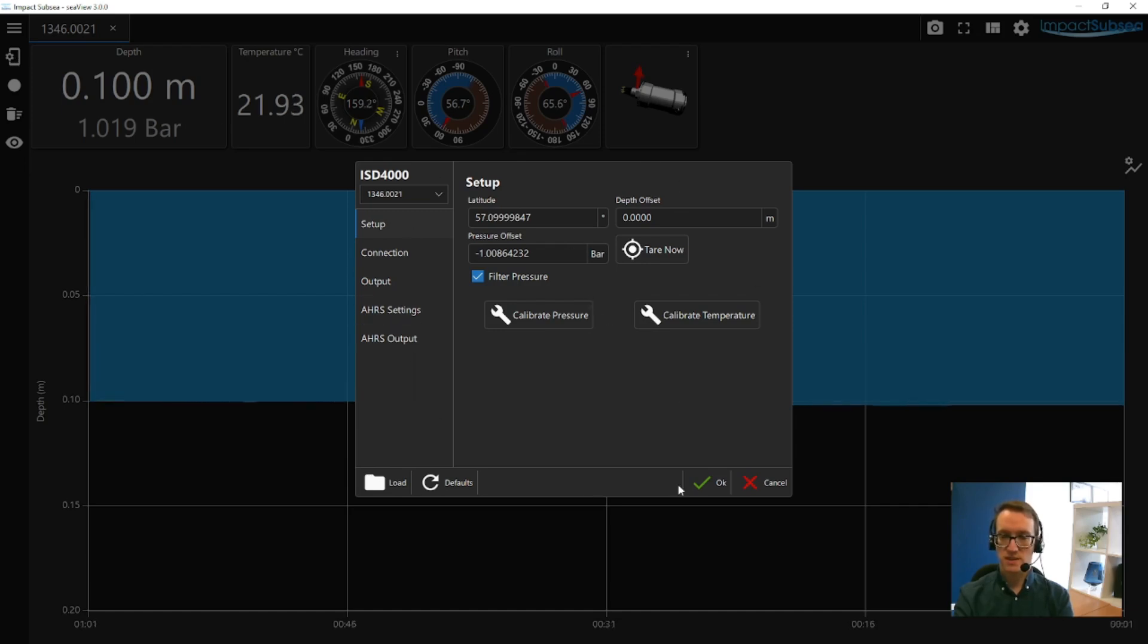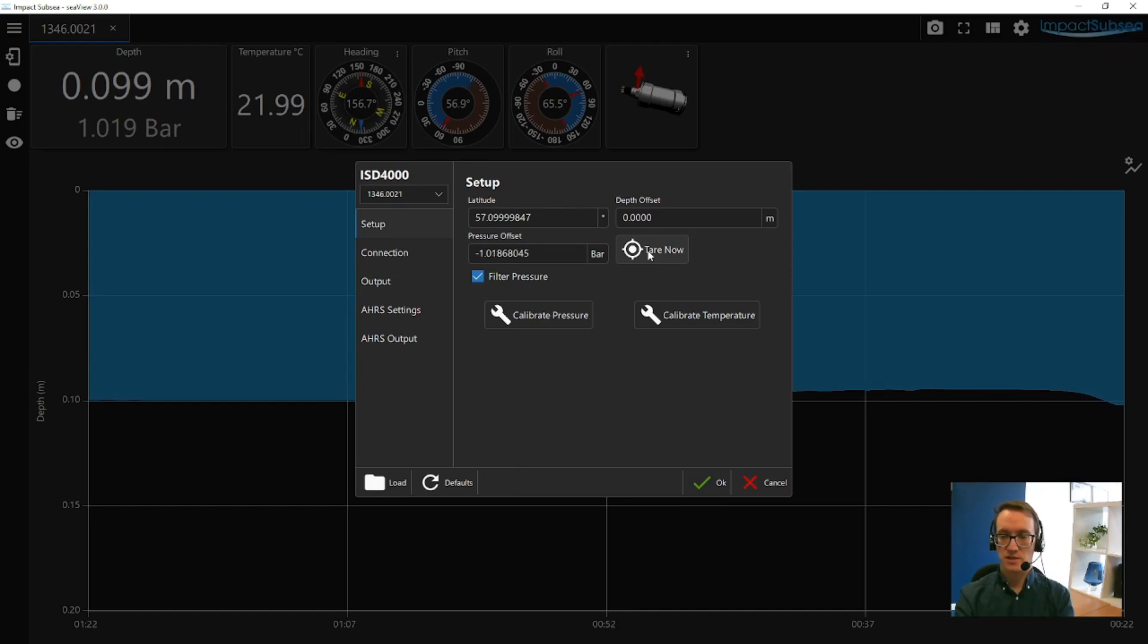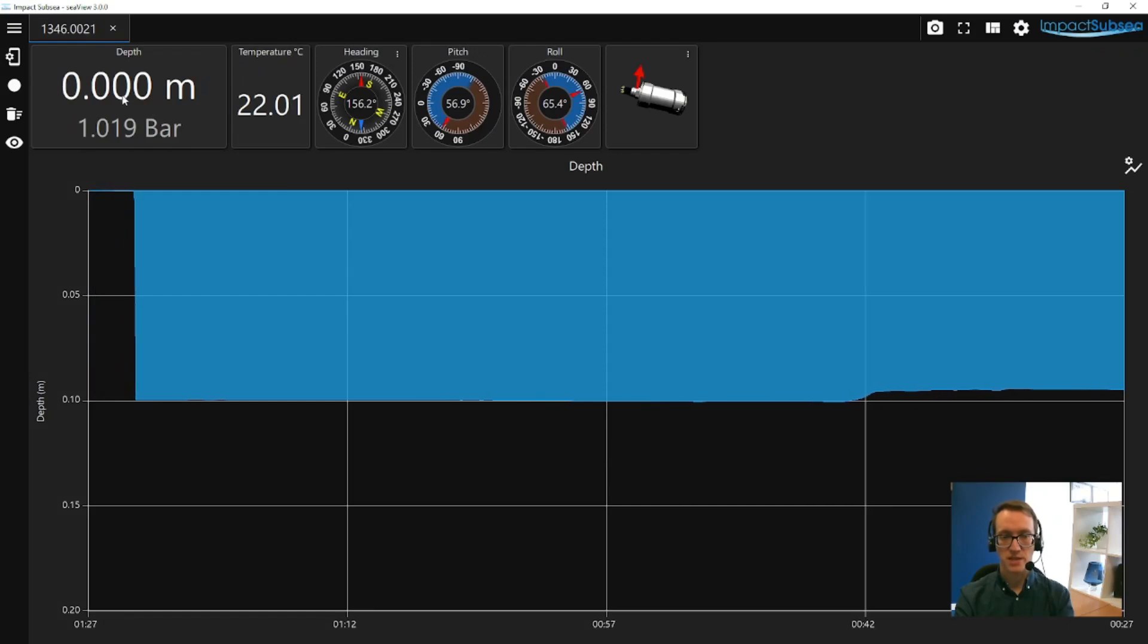So from here, the initial setup page, you can enter in the latitude of your area of operation. It's useful to enter this as it'll be taken into account when doing the pressure to depth conversion, as it'll take into account the local gravity in the area you're working in. You can then apply any depth offset or any pressure offset. You can tare the sensor immediately. If you click tare now, and then click the OK button, it basically zeros the depth. And you can see the depth has been zeroed in the top left-hand corner.